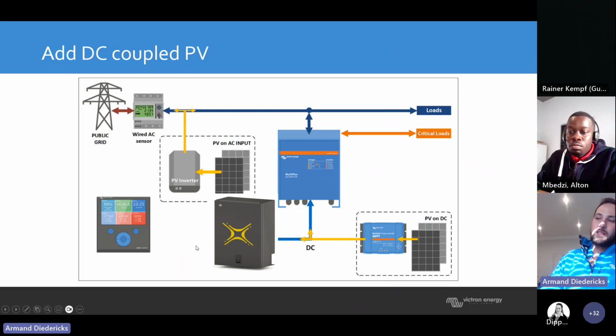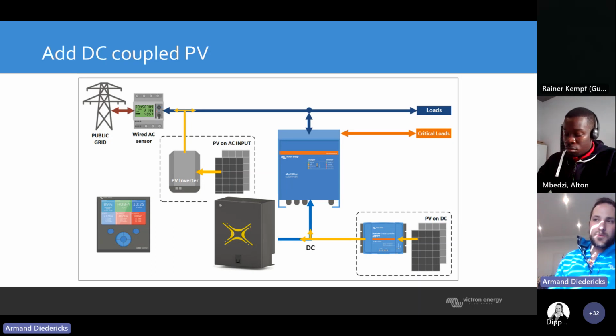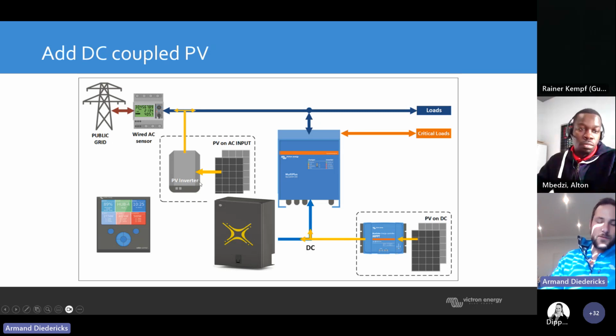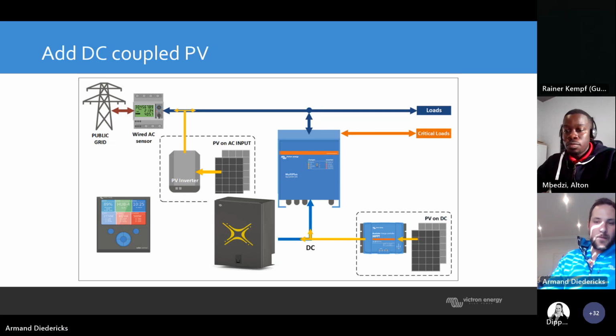So my suggestion, from multiple sites that we do, if it's a 180 kVA hybrid system or a 72 kilowatt hybrid system: install an Ethernet switch. Get your ISP, your internet service provider, whoever, it's actually the client's responsibility, to install a switch closest to the system. Get an Ethernet cable connected to the Cerbo and connected to the data manager of the Fronius. Then you won't have any problems. And set the programming parameters the right way. Right.